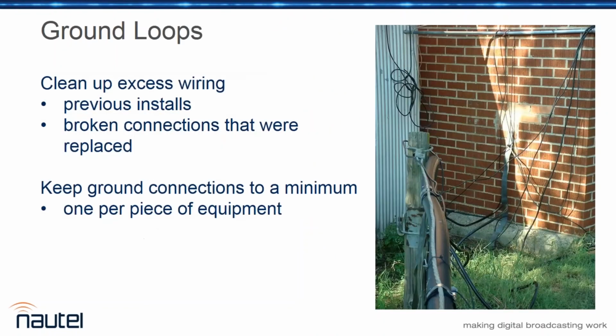This comes back to ground loops. So many times you'll run into a site, and a lot of radio sites have been around for years, and things get added, and added, and added. A lot of times they just get added on top of the old stuff, and you'll end up with wires going everywhere and strap going everywhere, and you don't really have a lot of control over what's going where. You end up with ground loops, you end up with hum. I'm sure almost everybody listening has got at least one story of going into a rack full of quad foam cable and finding one that had 120 volts AC on it.